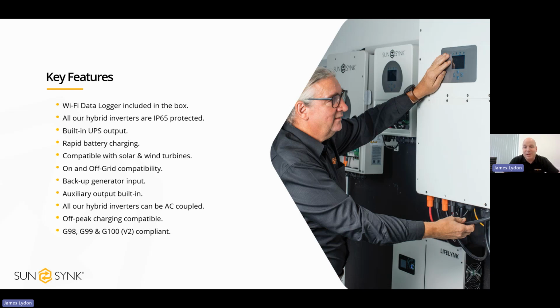That might be as simple as a double socket to give the end user access to power if there is a power cut, or you can wire in an essential circuit to that load output. That might be your lights, your fridge, your Wi-Fi. Obviously, in doing that, the earthing arrangements change, so you wouldn't need an earth rod. But like I say, that output is built into the inverters as standard.